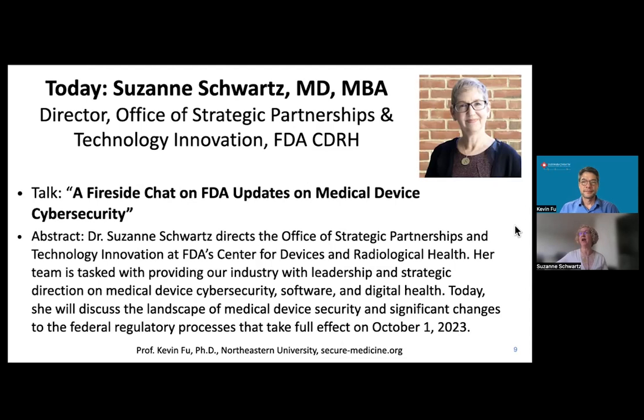So that capability is now part of being included within the pre-market submission, and there has to be evidence of that. If you remember, going back years ago when we put out the Medical Device Safety Action Plan, one of the items we signaled was the consideration for wanting to require just that. It's all part of trying to break out of this brittle legacy cycle of devices that end up on the market unable to be patched or updated, and that remain exposed surfaces for attack.